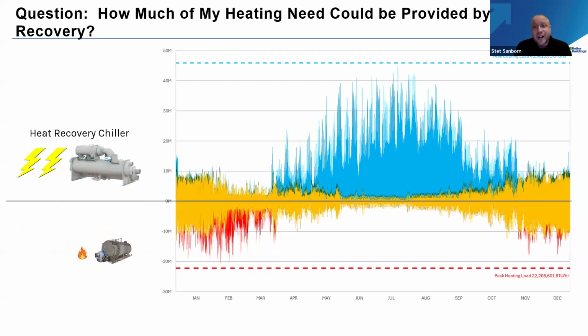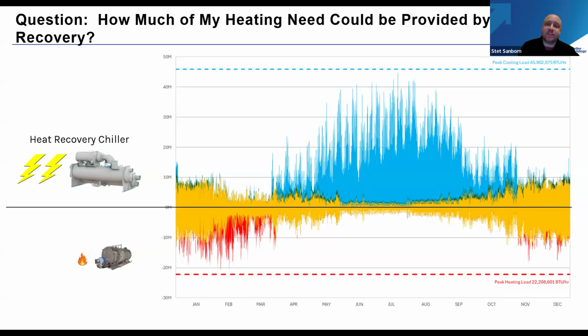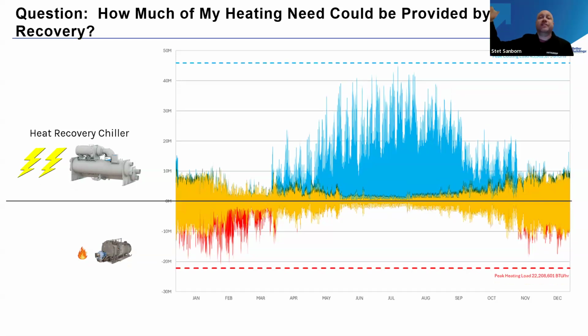So this is one of those options where now I'm looking at simultaneous heating and cooling. And Paul mentioned this, it's heat recovery. If instead of focusing on replacing your boiler with a heat pump, you actually, at end of life of your chiller, look at replacing your standard chiller with a heat recovery chiller. That chiller normally during cooling mode is dumping lots of heat to a cooling tower, or directly outside if it's an air-cooled chiller, just dumping that heat in the environment. You're spending a lot of money to get rid of heat when at the same time you actually want to provide heat. So a heat recovery chiller can do both things at once. It's a really amazing technology to use.